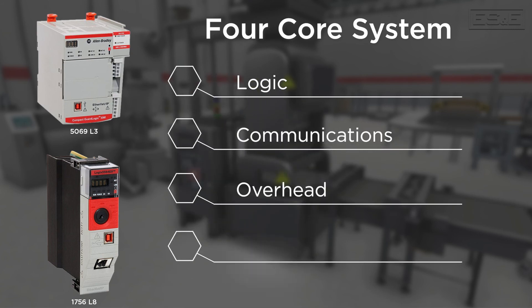The 5069L3 and 1756L8 controllers have a four-core system that contains a core for logic, communications, overhead, and safety. Having a dedicated core for safety allows the necessary redundancy checks between the logic and the safety cores. Now with a more appropriately sized system that works with the same CIP Safety network, Rockwell has been working to develop many more CIP Safety products and help provide a full safety system.